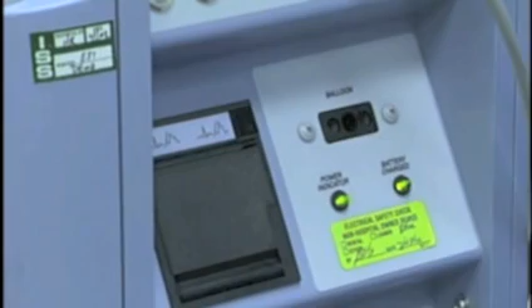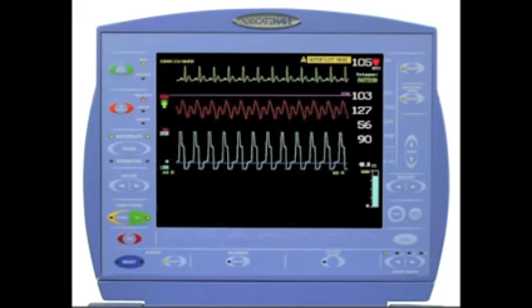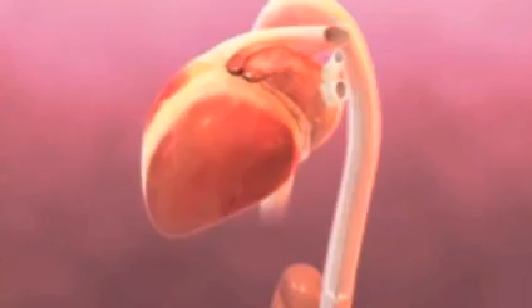The catheter is then connected to the pump console, containing the gas supply, the pump, the monitoring and the controller mechanisms. To effectively assist the circulation, the pump needs to know when to inflate and deflate, and to do so, a reliable physiological marker of the start and end of diastole is required. This is known as triggering. A number of triggers have been used.